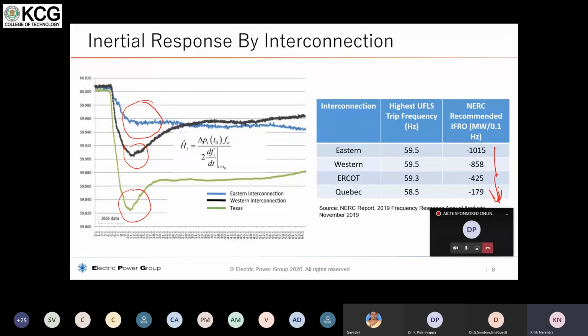But if you have more electronics such as renewables, then obviously the contribution of power will be higher because of this penetration of solar and wind. And once they go off from the grid, then you don't have any equivalent inertial support from the system, such as the wind and solar, and therefore you will have problems of dropping your frequency to a very marginal level where the protections and stabilities are sacrificed in the system.